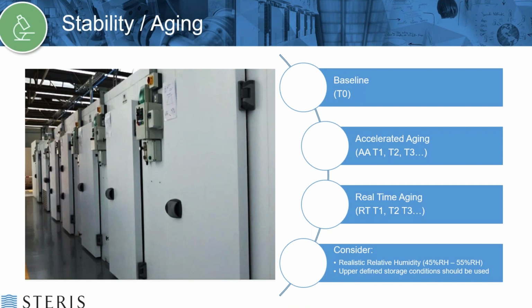Typically, you would do the ultimate shelf life you want to achieve. Say you've got a 5-year shelf life for your product, and there will typically be at least one, if not more, interim time points as well, just to give you some additional data. And that would apply for both accelerated and real-time aging. Real-time aging is exactly what it sounds like. If you have a 5-year shelf life, it's going to sit for 5 actual years, followed by some package testing. For accelerated aging, the higher the temperature you perform the aging at, the faster that acceleration will be.